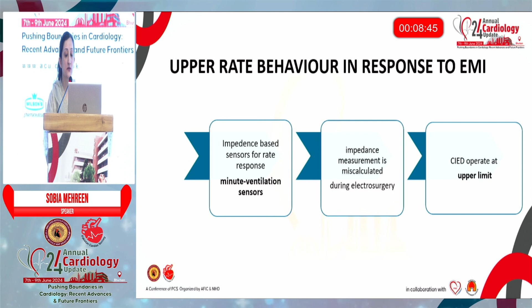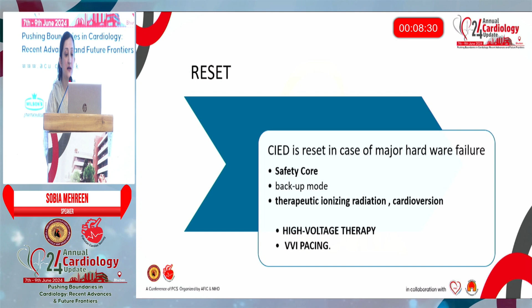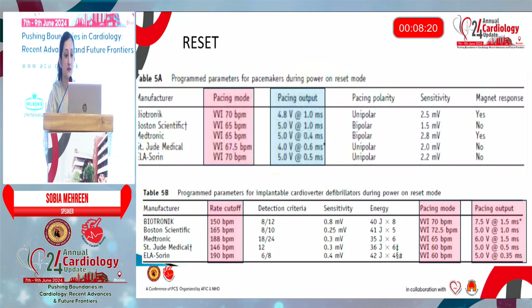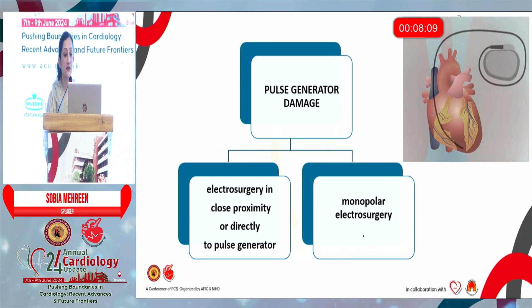The device can be reset to factory settings in case of major hardware failure that occurs in case of exposure to therapeutic radiations and cardioversions. The device paces with high voltage treatment in VVI pacing mode. The different manufacturers have their own preset and pre-programmed pacing modes and pacing outputs for the reset mode in both pacemakers and ICDs. The permanent damage of the pulse generator can occur if the electrosurgery is applied directly over the pulse generator or in case of exposure to monopolar electrosurgery in close proximity.